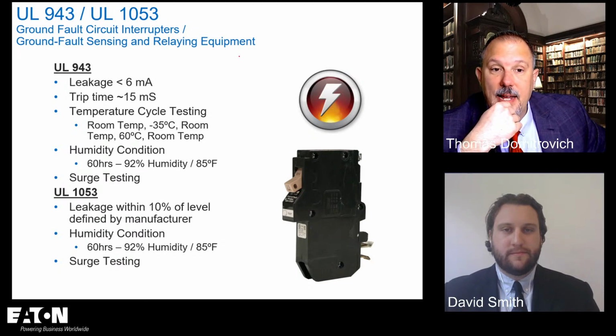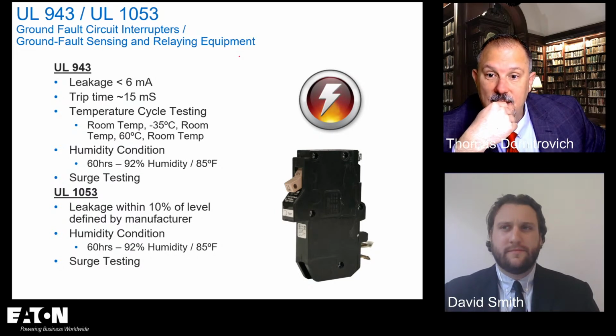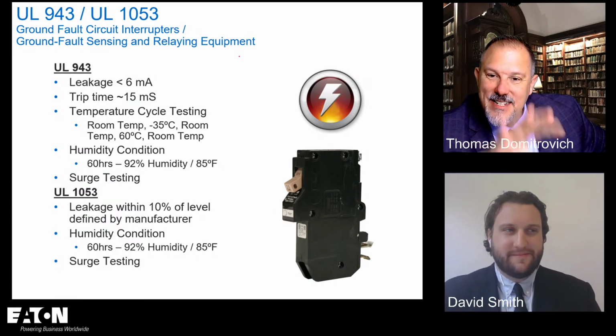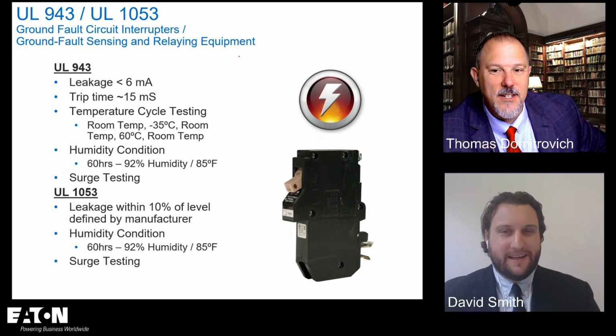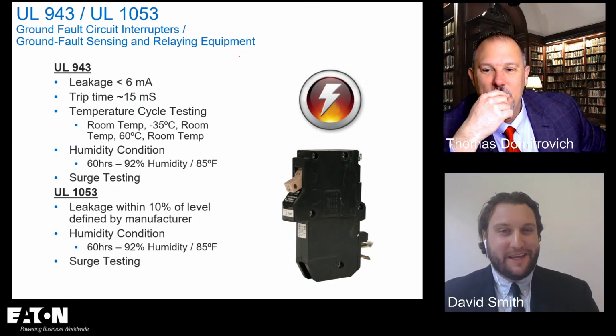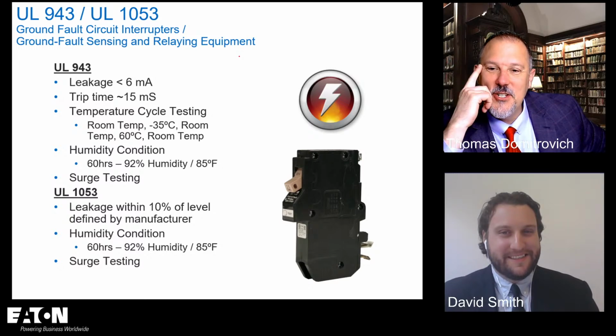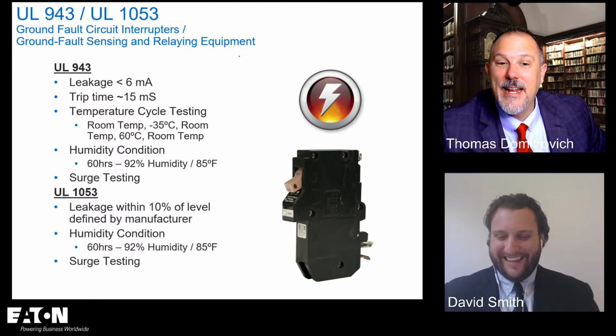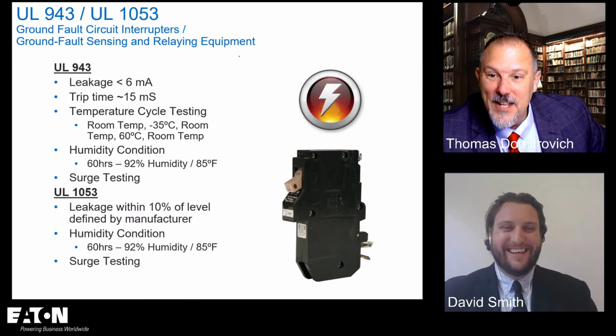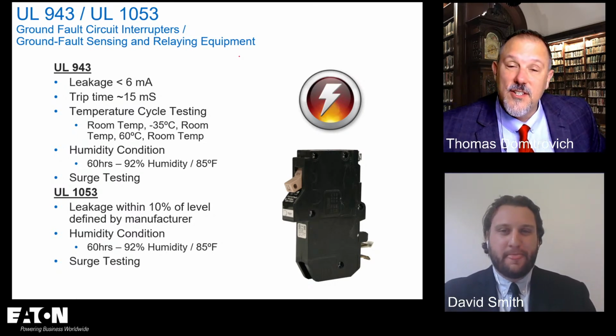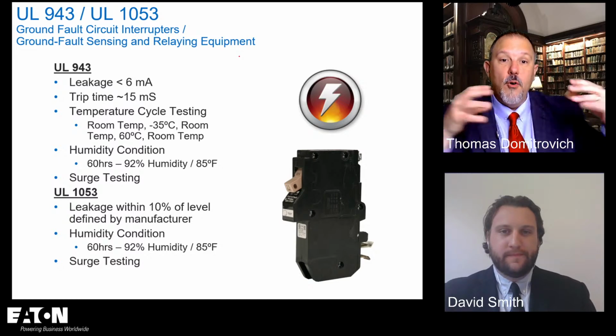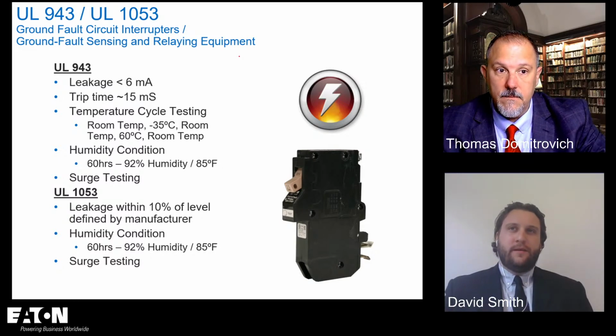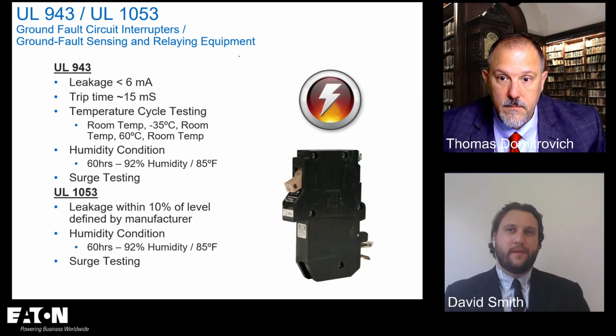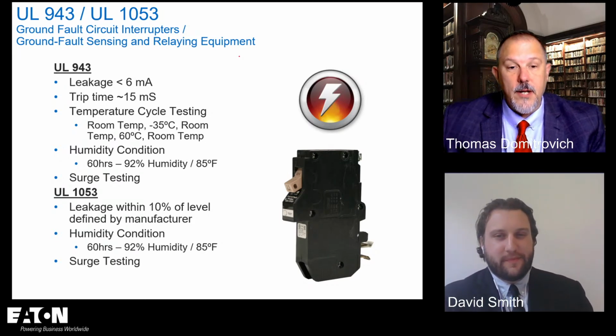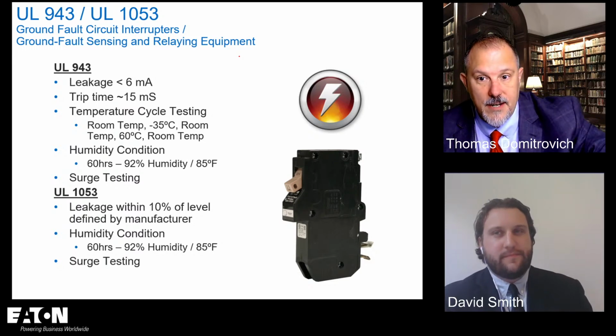David, can I buy an AFCI, GFCI receptacle? A receptacle that has AFCI. This is an easy question. Just spit it out. I'm going to say yes. Oh, very good. Yes, you can. So you can buy an AFCI, GFCI receptacle. I can buy an AFCI, GFCI circuit breaker. So I can put both technologies in the exact same device. I can buy them separately. I can have an AFCI breaker or a GFCI breaker. I can have an AFCI receptacle or a GFCI receptacle.